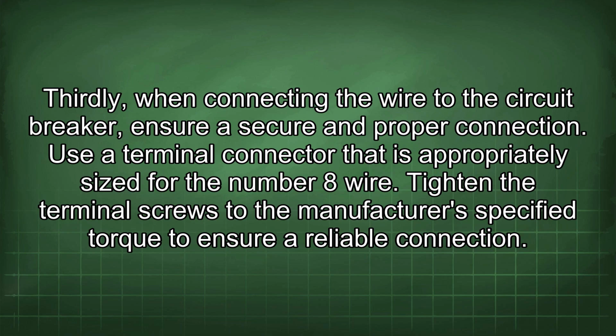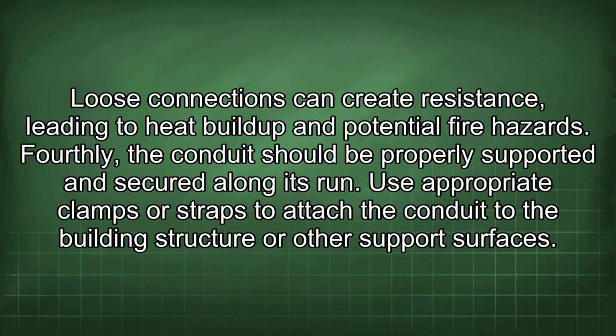Thirdly, when connecting the wire to the circuit breaker, ensure a secure and proper connection. Use a terminal connector that is appropriately sized for the number 8 wire. Tighten the terminal screws to the manufacturer's specified torque to ensure a reliable connection. Loose connections can create resistance, leading to heat buildup and potential fire hazards.